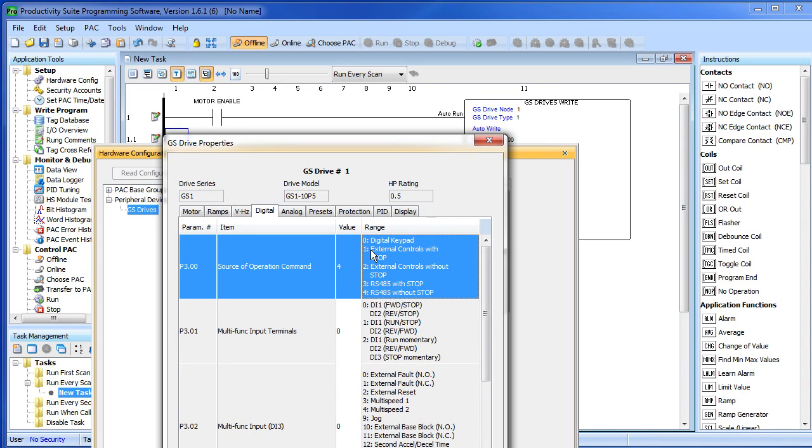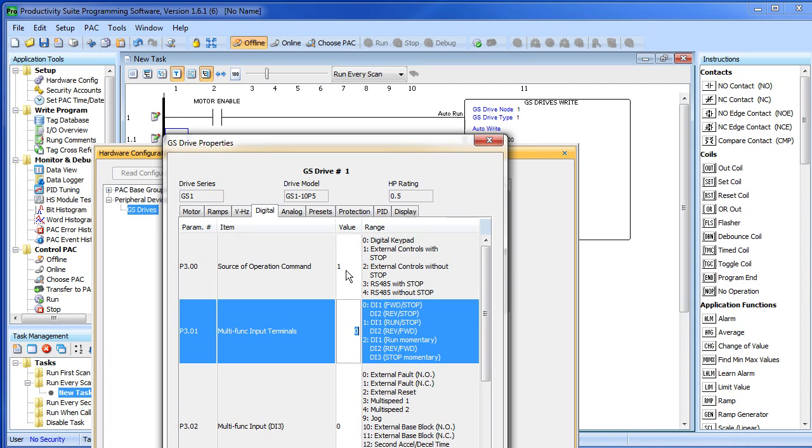If you select an external source, let's say number 1 right here which says use the external source with the stop button on the keypad enabled, now you have to tell it how to configure the IOs. You do that with parameter 3.01.